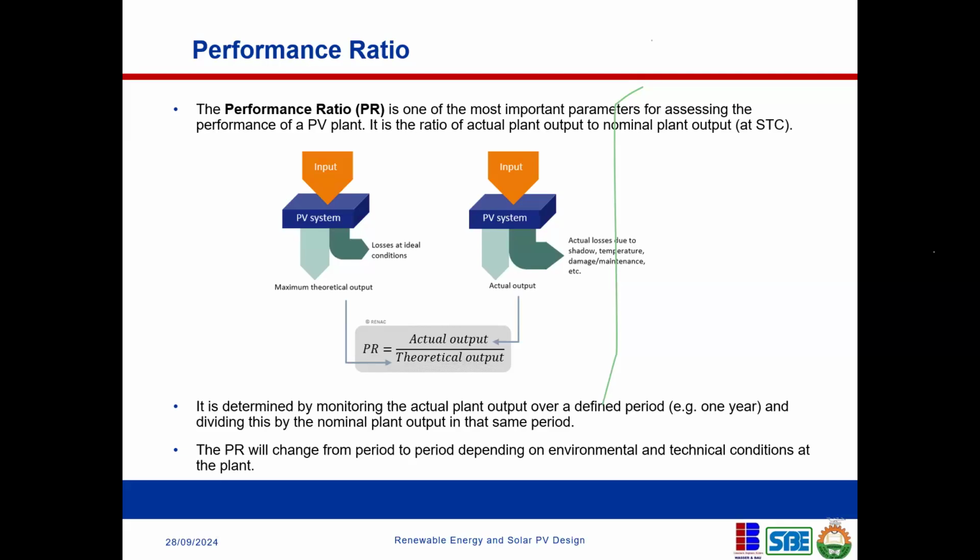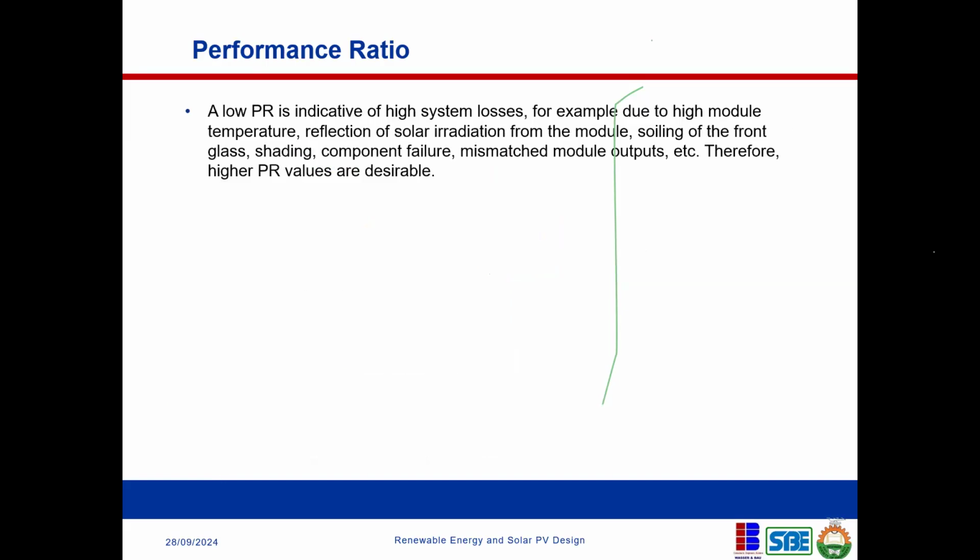I've had an installation done in the past, and over time, I got a complaint that it is not working. And obviously, that was during the dry season, and of course, dust would have settled on the panel. What we needed to do was to go and clean the panel, and things started working again. So there needs to be constant follow-up to make sure you get the best out of these installations.